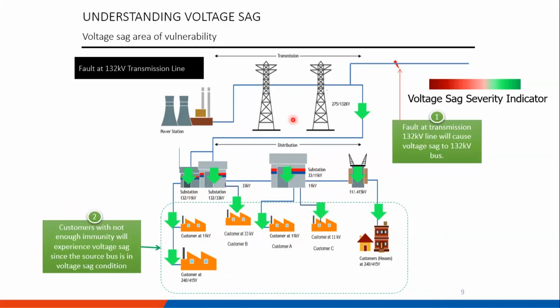Okay, another example: a fault at the transmission line. Let's say we have a big transmission line here connected everywhere, and there's a fault at transmission 132 kV. Since there's a fault here, there will be some voltage sag. However, since the transmission line is quite a distance away from the source, maybe the voltage sag is not that severe.